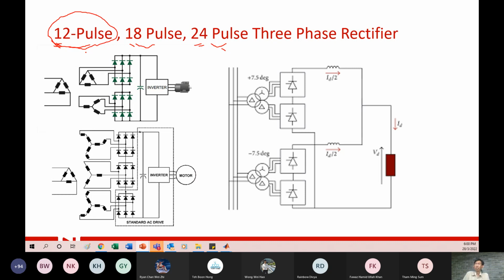How they did it is very simple. They calculate. Most of the industry uses a single tuned filter. If the single tuned filter is much more expensive, then they go for 12 pulse, and the single tuned filter they use is much cheaper compared to just 6 pulse. After some intensive study, they found that 12 pulse is right in the middle. It won't reduce the harmonics below the standard, but you can save some cost compared to just using 6 pulse. So to be very honest, personally I only see up to 12 pulse. Don't ask me where you can see 18 and 24 used.